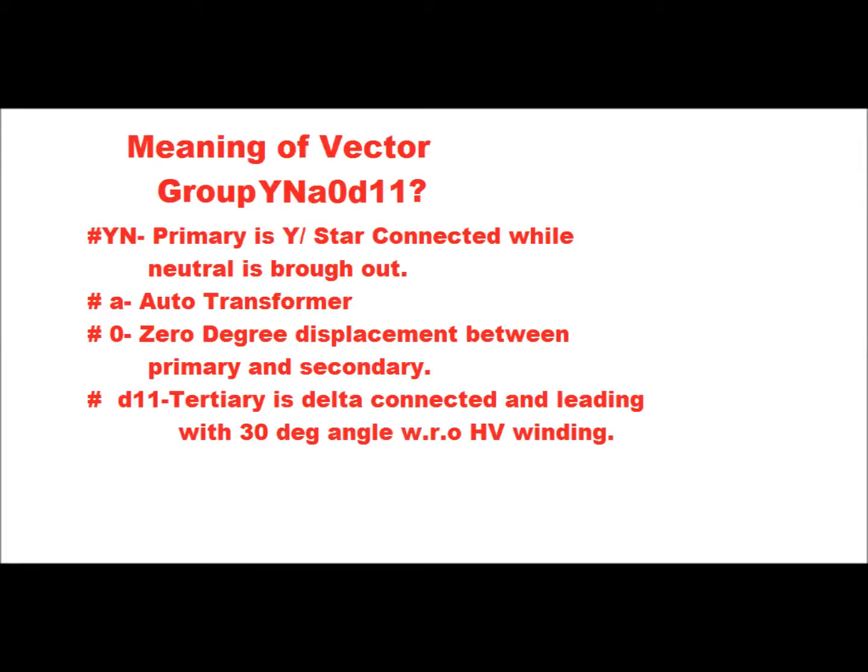What is the meaning of the vector group YNA0D11? Here capital Y and capital N stand for primary is star connected while neutral is taken out. N stands for neutral, A stands for auto transformer. Zero means that in between primary and secondary there is zero degree displacement. D11 — D in small letter denotes that tertiary is delta connected and leading with 30 degree angle with respect to HV and LV.